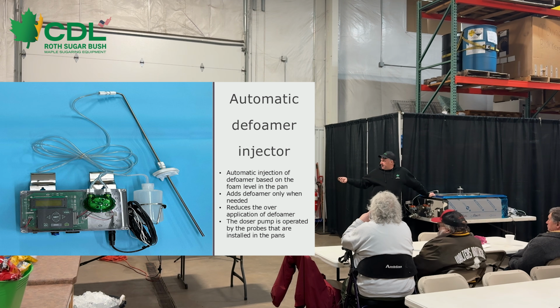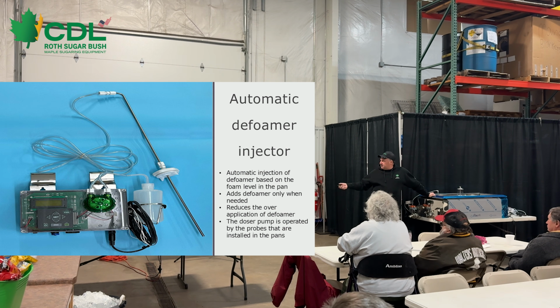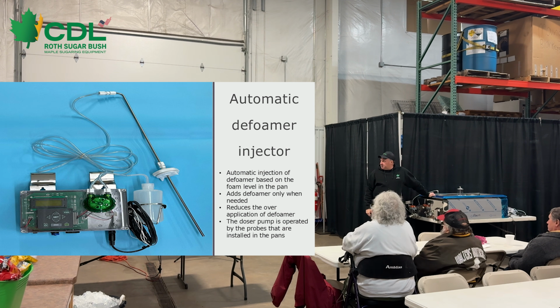This particular device has been on the market now for just a couple of years. What it does is, we have a probe that goes down into the pan and a small ground clip or connection clip that connects to the pan. When the foam in the pan starts to rise, it hits this probe, reads that conductivity, starts the pump, and automatically puts defoamer into the pan. Once the foam level drops inside the pan, the pump shuts off.